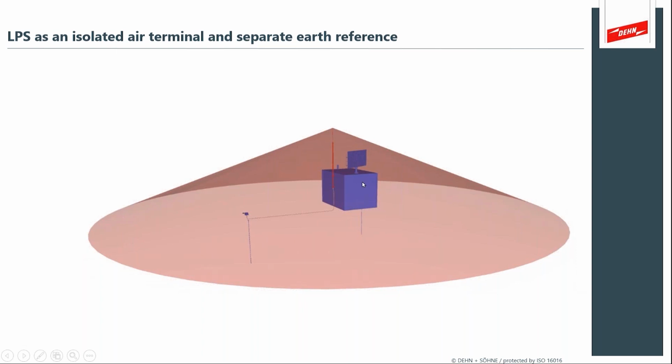And so what was important for this customer is that they protect this structure from lightning and from the ground potential rise that would occur if the soil induces that ground potential rise into the structure itself. So in one nice illustration, you have all those aspects we've discussed, including separation distance.